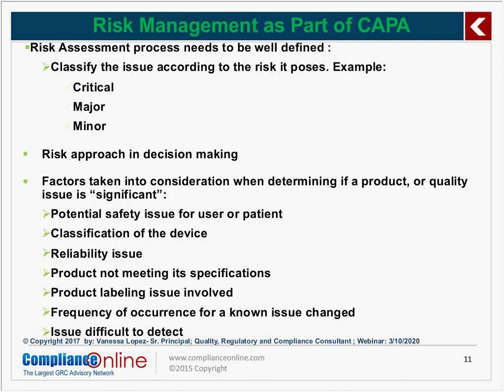All three of these may be used in terms of risk, and some companies define them for the recall definition. So, therefore, critical would be that there is a reasonable chance the product will cause serious health problems or death. That would be like a recall type 1. Major risk would be less serious.